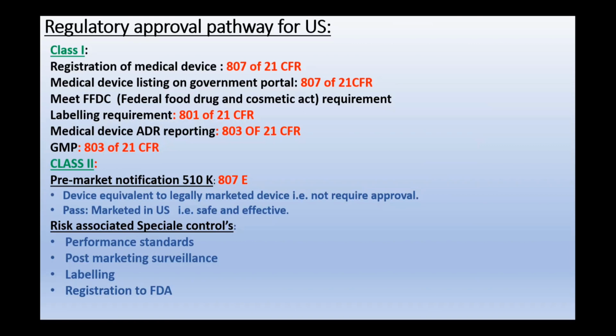For class 2 medical devices, the pre-market notification, that is Part 807E of 21 CFR, has to prove the device is equivalent to a legally marketed device that does not require approval. Then the device is passed and marketed in the US, considering that it is safe and effective.